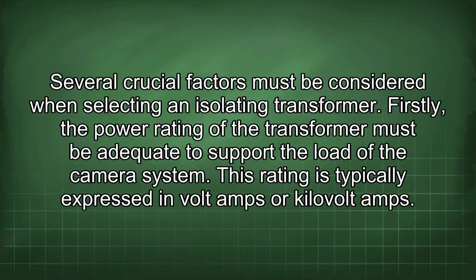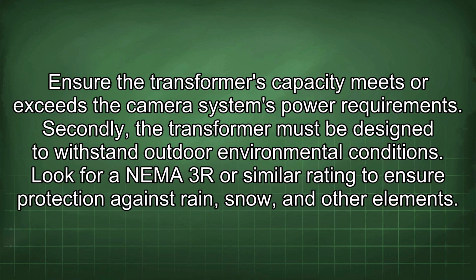Several crucial factors must be considered when selecting an isolating transformer. Firstly, the power rating of the transformer must be adequate to support the load of the camera system. This rating is typically expressed in volt-amps or kilovolt-amps. Ensure the transformer's capacity meets or exceeds the camera system's power requirement. Secondly, the transformer must be designed to withstand outdoor environmental conditions. Look for a NEMA 3R or similar rating to ensure protection against rain, snow, and other elements.